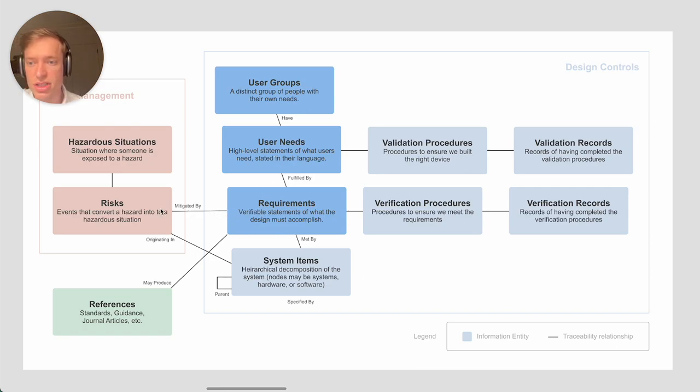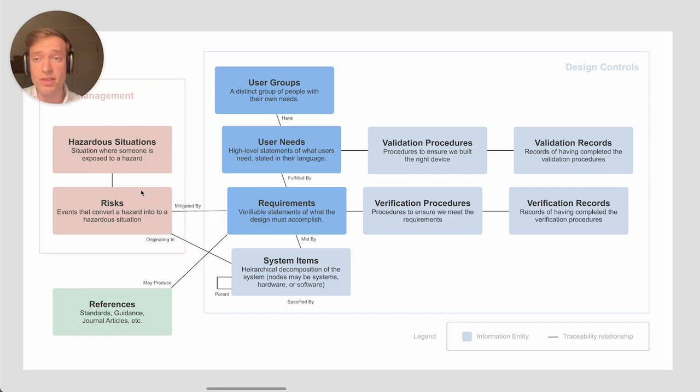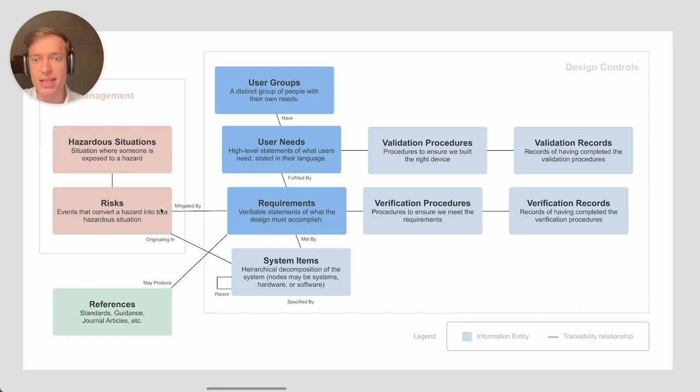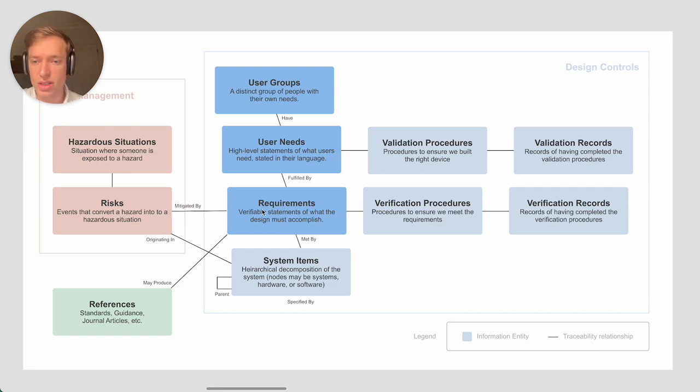Now the traceability relationship to risk. As part of your risk management, you will have identified safety risks and cybersecurity risks. Some of these risks might be mitigated by the design of the device itself. In that case, you'll need to write requirements for that mitigation.